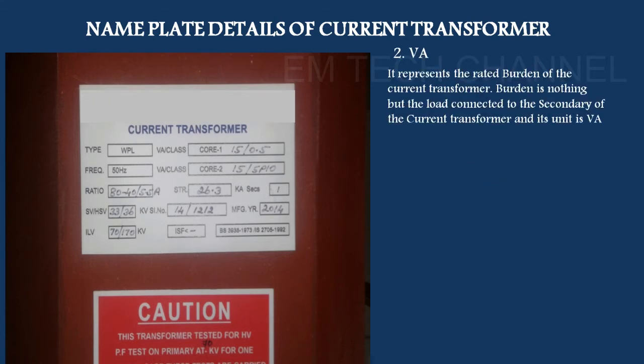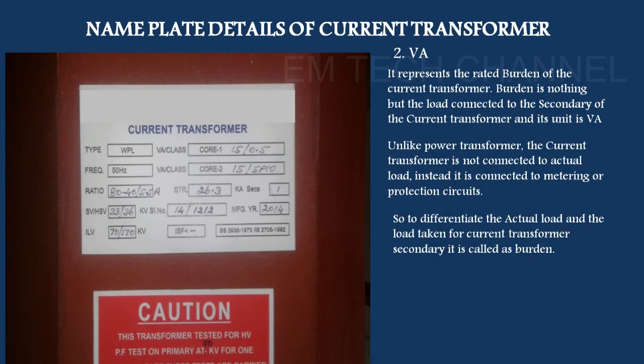VA is the rated burden of the current transformer. What is connected to the CT secondary? We can load a burden on it. We can use the CT secondary with a protective relay. That connected load is called the burden. The load on the CT secondary — such as a meter, wire resistance, or relay — all together make up the burden.